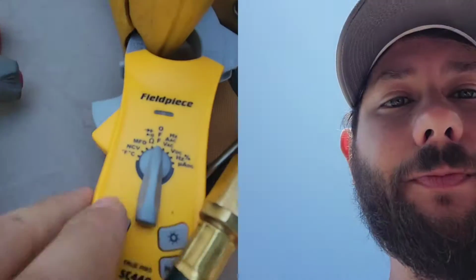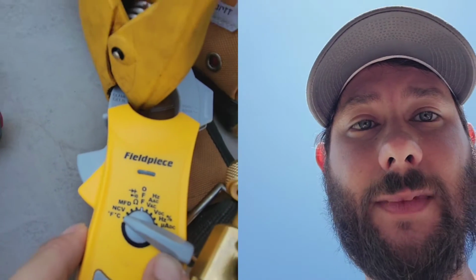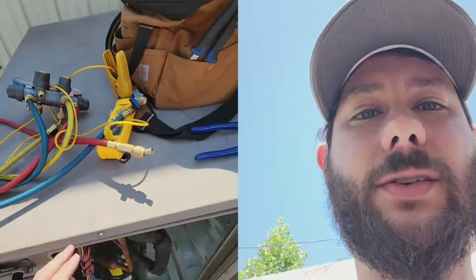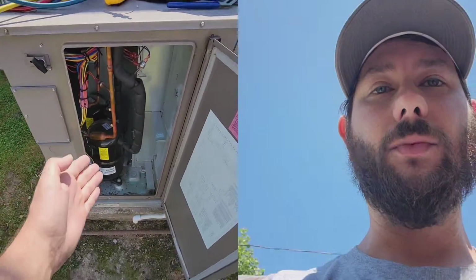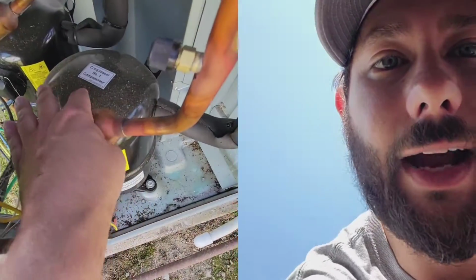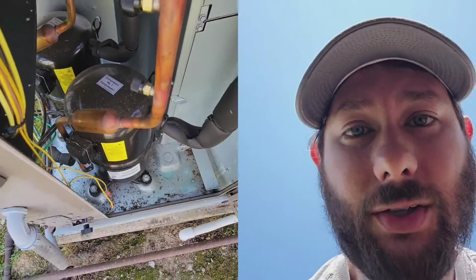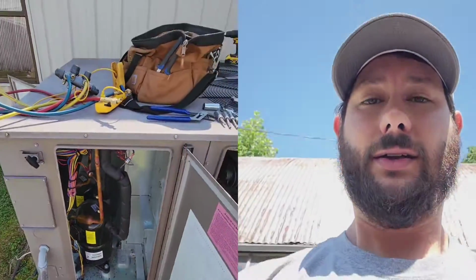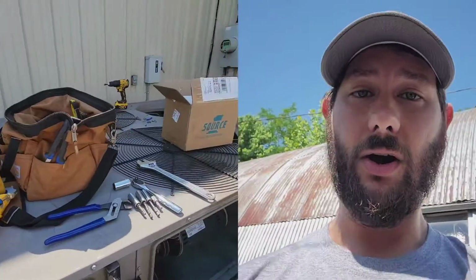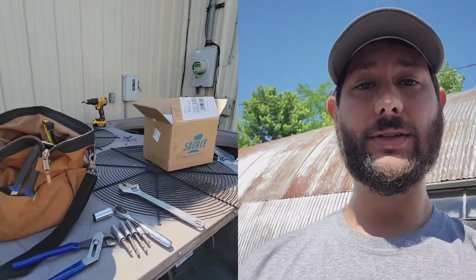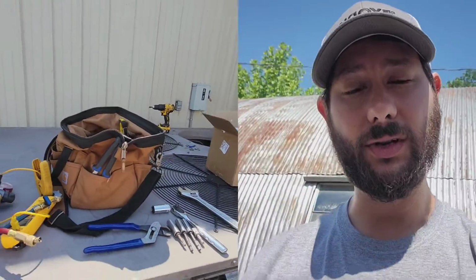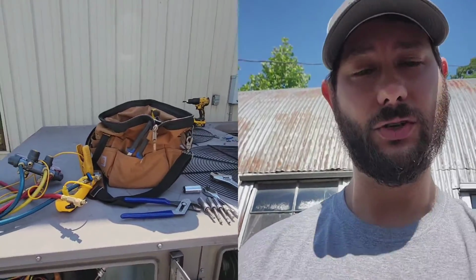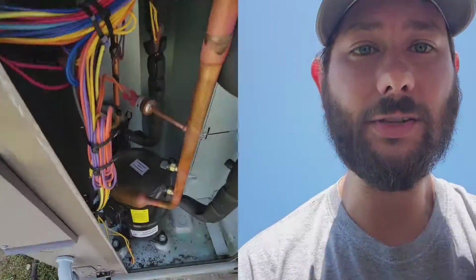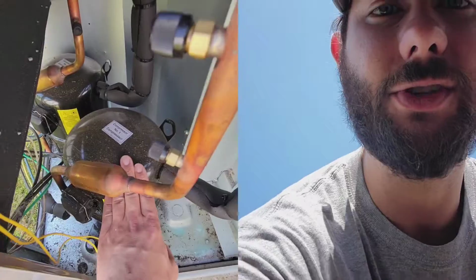Then you've got your meter, which checks Fahrenheit, and then you got your temperature probe. So you got two circuits. Circuit one's going to come on first right there, and that's the Y1 call. When you get a signal from the thermostat, that means R and Y have 24 volts. Then you're going to have 24 volts to common and yellow, which is your first cooling call. You're going to check 24 volts there. Compressor's going to come on.